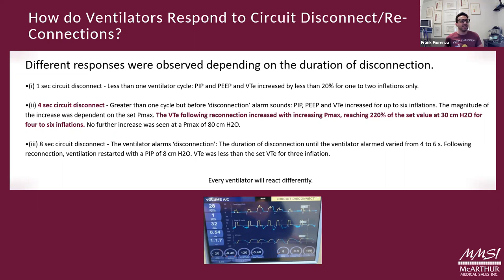So every circuit disconnect is more dramatic than just the disconnect itself. This will vary ventilator to ventilator - they all react differently, but they're all computer chips looking for a biofeedback mechanism to get that information back from the patient and find those ideal settings.